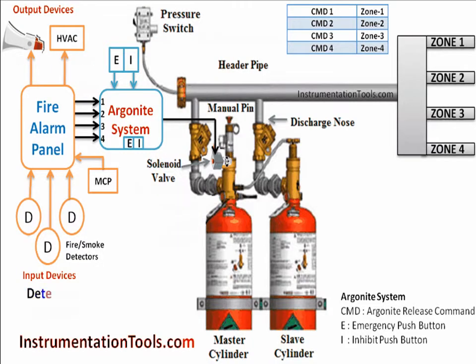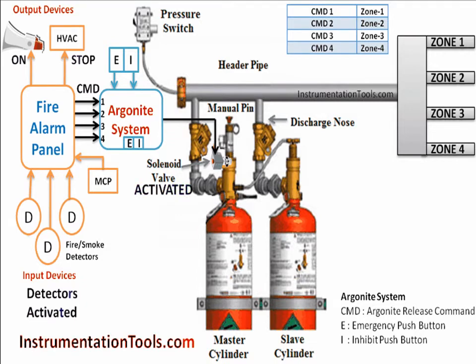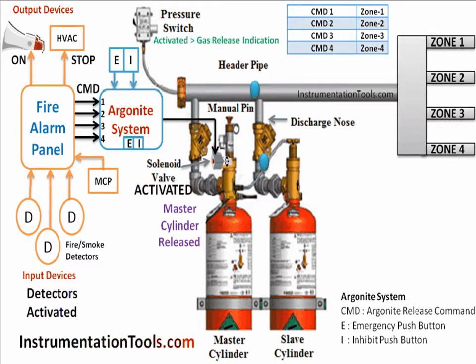Argonite System Operation: When any fire incident happens, fire and smoke detectors will be activated. These detectors give a signal to the fire alarm panel. The fire alarm panel activates the hooter, stops the HVAC unit, and sends an Argonite Release Command to the Argonite System.